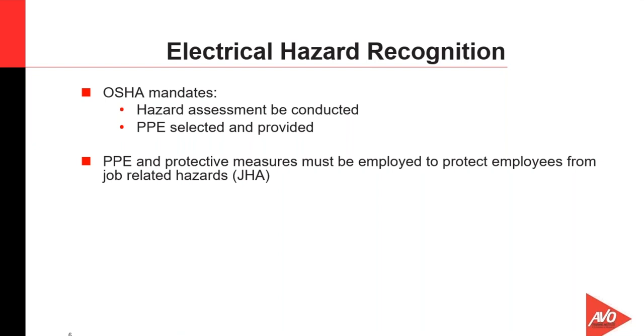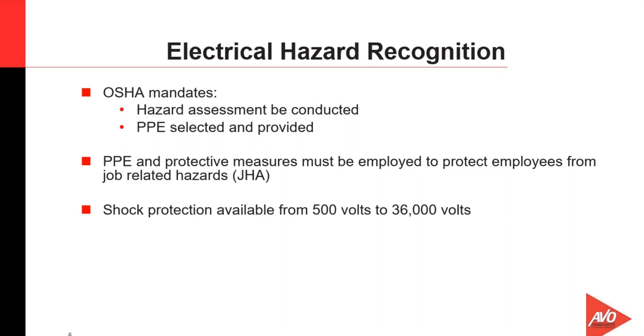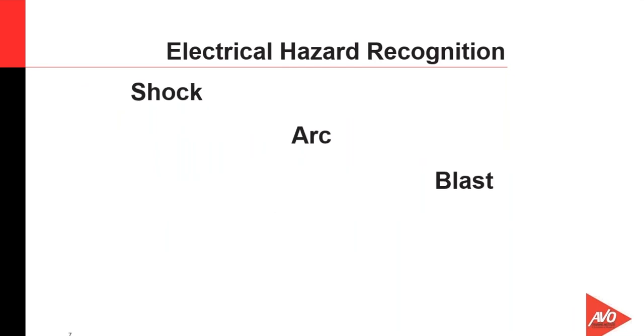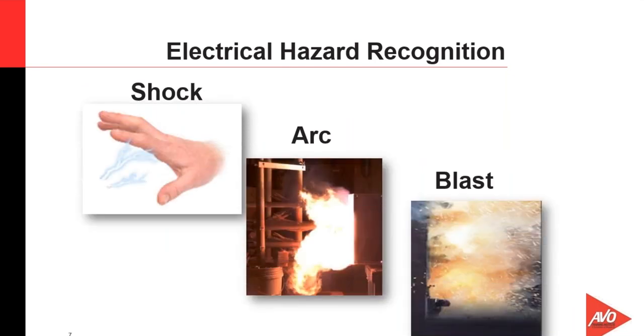So in the cable testing and cable fault locating world, we have numerous tasks and very complex pieces of equipment, most of which can create lethal shock. We need job hazard analysis performed and procedures written to actually perform these types of tasks. We have shock protection available from 500 volts to 36,000 volts. In addition to that, we have arc flash and blast protection also available in various levels of protection.